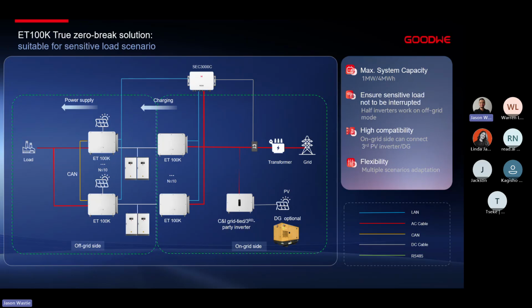We do this to be able to run extremely large systems with 0 millisecond transfer, extremely volatile systems that cannot have up to even 1 millisecond of downtime. We run with a solution like this to ensure that any of our sensitive loads do not become interrupted during any transfer or switching time. Even though we can get down to 4 milliseconds of transfer, there will be some application scenarios where that is still too slow. So this is for things like massive data centers or huge manufacturing plant operations where we cannot afford any downtime at all.